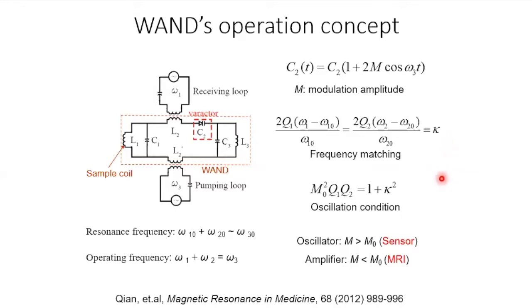So I should also mention that if the pumping signal is strong enough, the sensor is an oscillator that will spontaneously emit a sustained oscillation signal. The sensor will be used to detect physiological signals, even outside the NMR scanner. But when the oscillation signal is small, not sufficient, we operate the sensor as an MRI amplifier. And the amplification factor, the gain, is equal to the square of the inverse of the relative deviation from the oscillation condition.